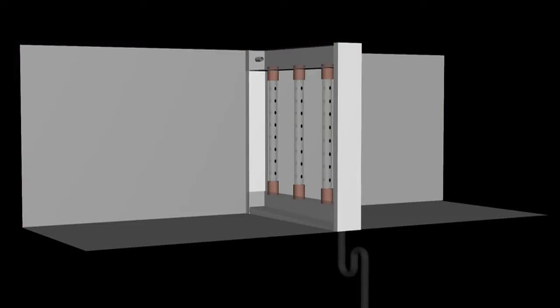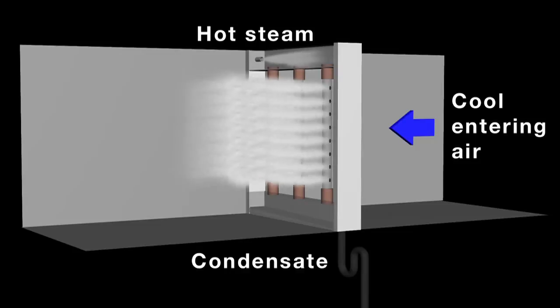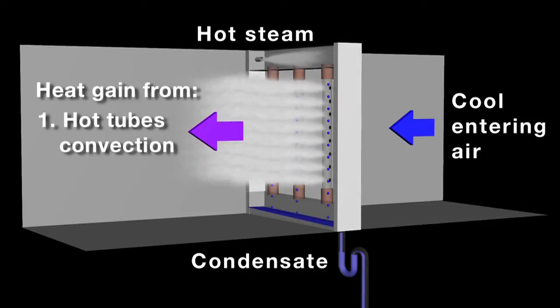In a duct or air handler, cool air flowing across hot dispersion tubes causes some steam inside the tubes to condense, thus maintaining the high temperature of the dispersion tubes. The convective heat transfer resulting from cool air flowing across hot dispersion tubes increases air temperature downstream of the dispersion tube assembly.